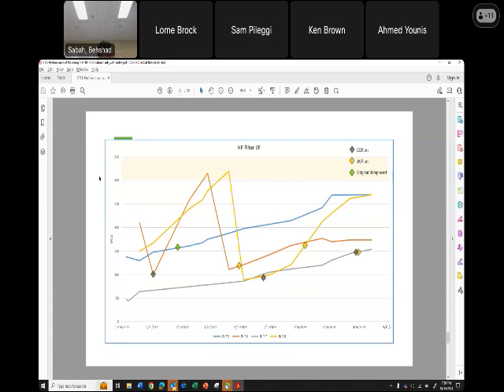Okay, and the filter delta P. On the orange line, the unit 6, where we have that spike, just ignore that because that was a pump train change. After we turned the electrostatic and the IX resin on, we see the rate of delta P increase unchanged.